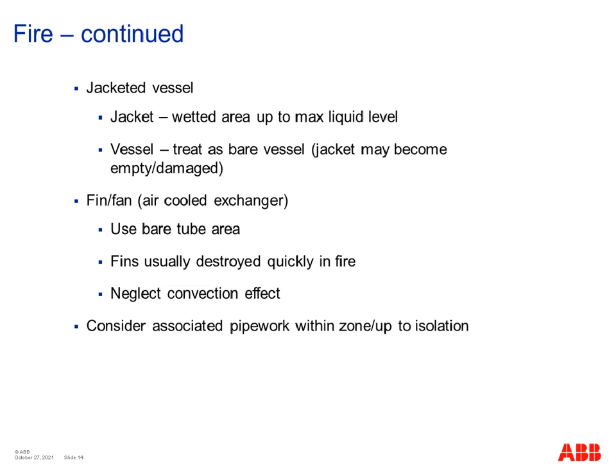For a fin fan cooler, you would use the bare tube area, because although you're going to have fins on the tubes, those fins may be destroyed quite quickly in the fire and therefore offer no protection after that point. You would neglect any cooling from convection, because that's going to be pretty negligible compared to the heat input from the fire. And you would consider the adjoining pipework, in any case, up to the extent of the fire zone boundary or up to the next isolation valve.